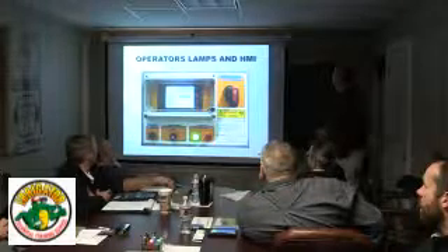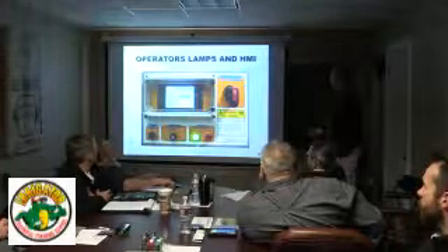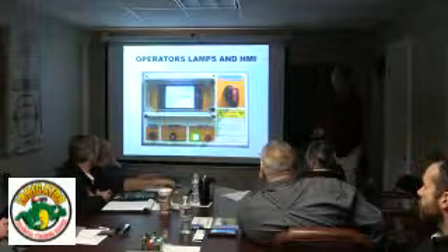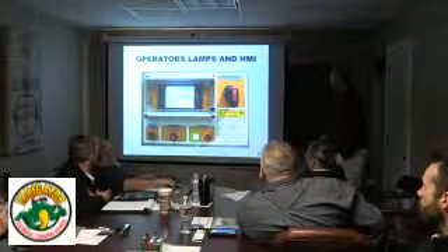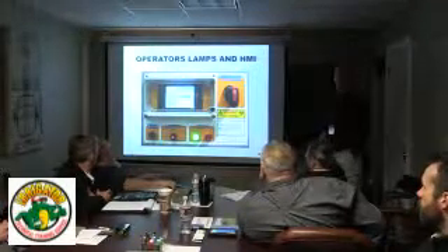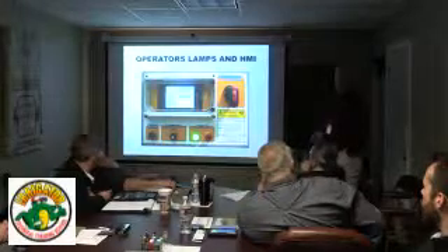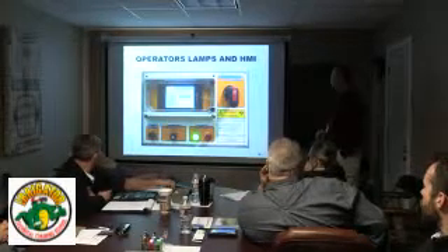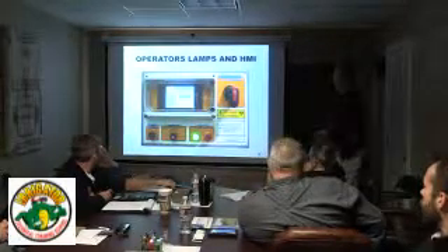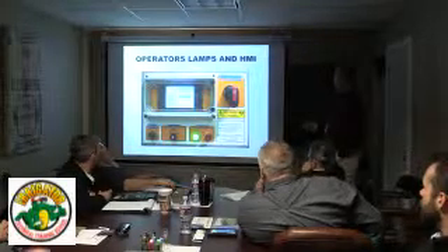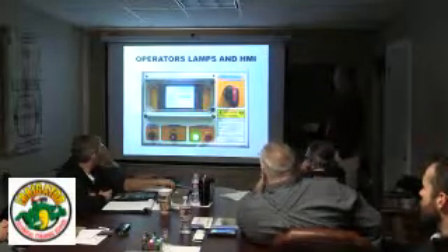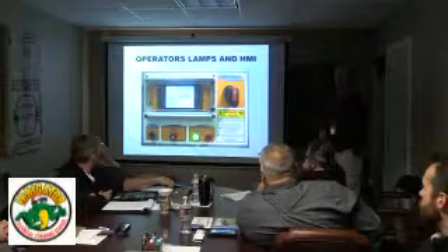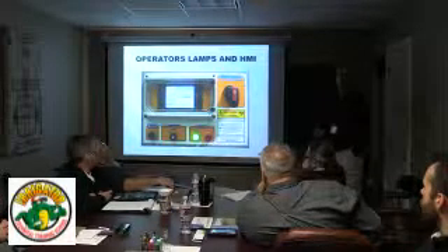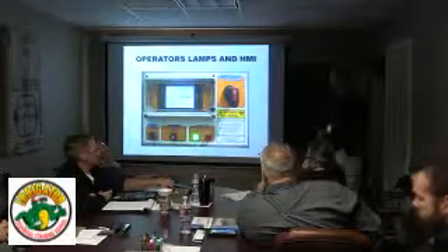Another one with a little different touch screen on it. This one has normal power fail buttons. The red light will come on anytime there's a fault. If power's okay, you'll see the green and the red. But the red light will come on if there's a fault. It should also display a fault right here where it says system normal. It'll display a fault, you know, low water, high pressure, low flow.